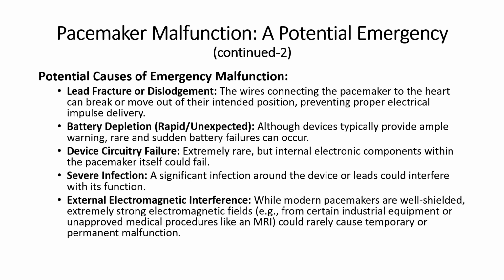Potential causes of emergency malfunction. Lead fracture or dislodgement. The wires connecting the pacemaker to the heart can break or move out of their intended position, preventing proper electrical impulse delivery. Battery depletion, rapid or unexpected. Although devices typically provide ample warning, rare and sudden battery failures can occur. Device circuitry failure, extremely rare, but internal electronic components within the pacemaker itself could fail. Severe infection, a significant infection around the device or leads could interfere with its function. External electromagnetic interference. While modern pacemakers are well shielded, extremely strong electromagnetic fields, e.g., from certain industrial equipment or unapproved medical procedures like an MRI, could rarely cause temporary or permanent malfunction.